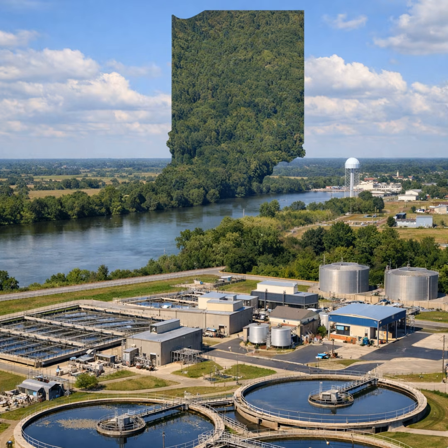And then the step feed activated sludge process is where incoming influent wastewater is diverted into different portions in different places in an aeration tank. So it's given in different steps. It's not like a plug flow, where a slug of wastewater comes in at one end, goes through, and goes out the other end. It's a step feed, where it's injected or introduced in different portions of the activated sludge aeration tank.